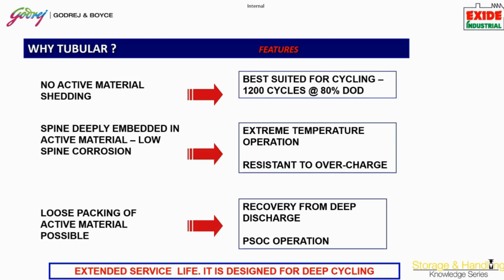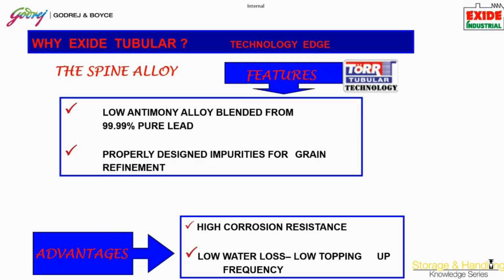There's something about the spine alloy, which imparts strength to the active material. This spine alloy is also 99.99% pure lead, but sometimes 0.01 to 0.03% impurities are added, like antimony, to provide corrosion resistance and strength to the spine, because lead itself is a very malleable and ductile metal. This cannot withstand it if heavy positive active material is to be deposited for higher capacity, so any range, size, or thickness of pure lead structure will not support this.